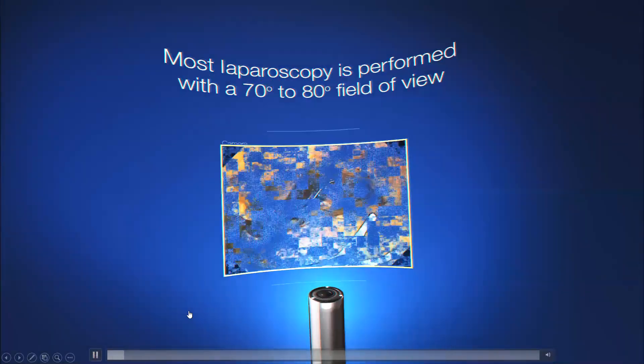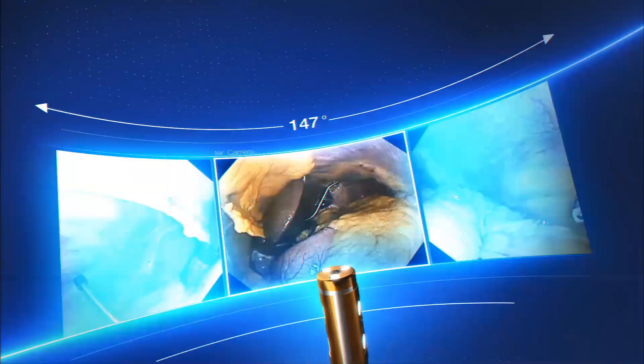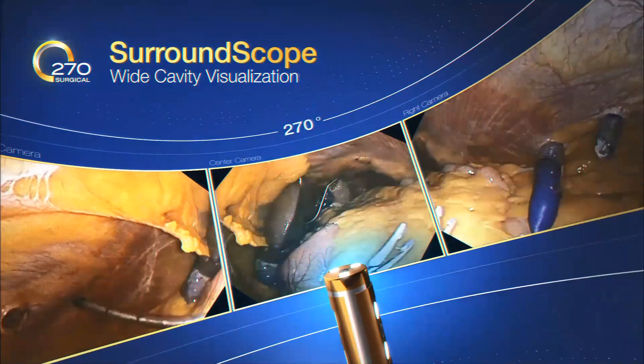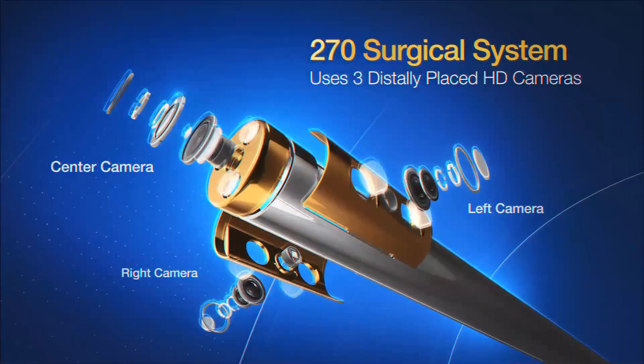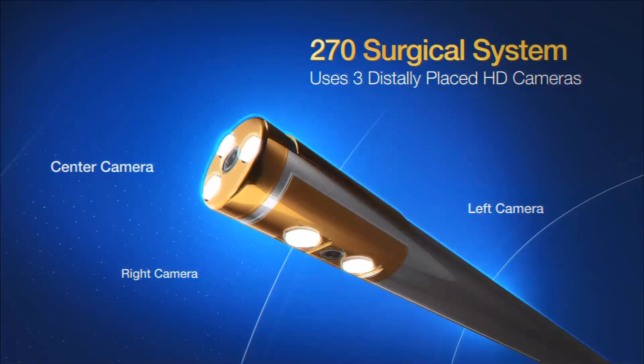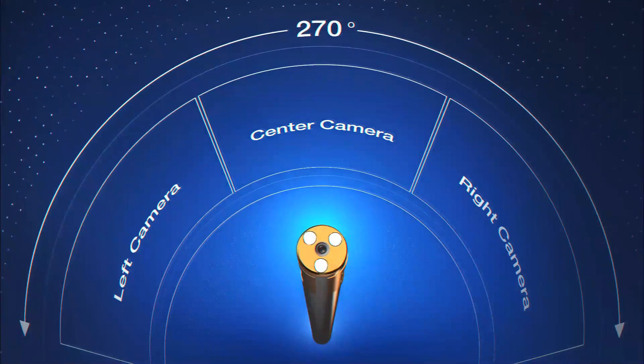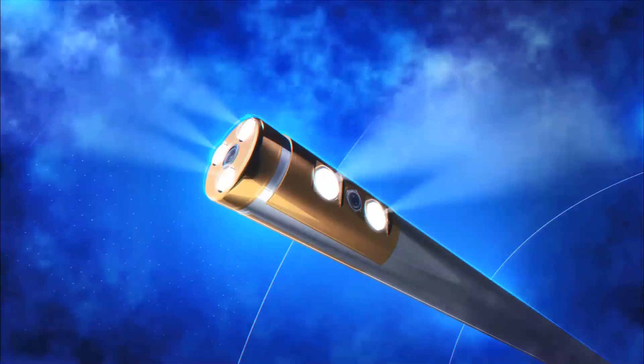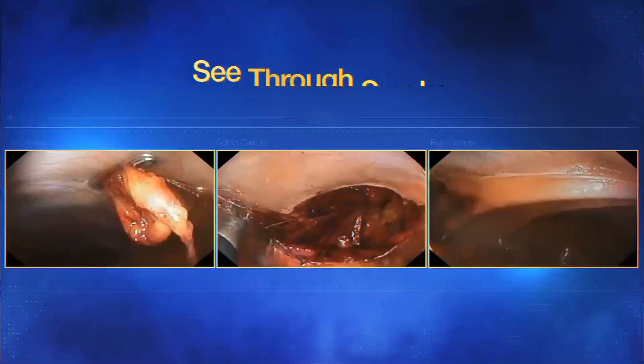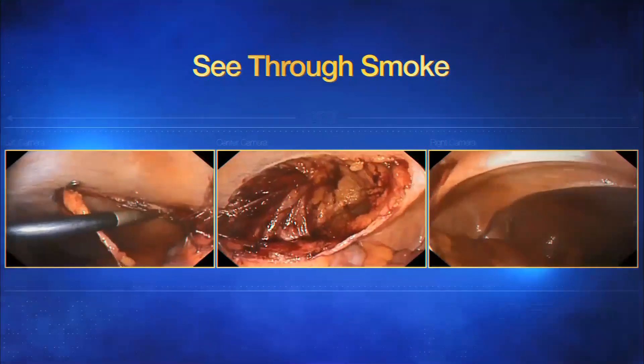Most laparoscopy is performed with a 70 to 80 degree field of view. With SurroundScope wide cavity visualization, the 270 Surgical System uses three distally placed HD cameras, greatly expanding the field of view and potentially eliminating the need for a person to hold the camera. LEDs gently warm the scope eliminating fog, while the proprietary camera sensors enable caregivers to see through smoke.